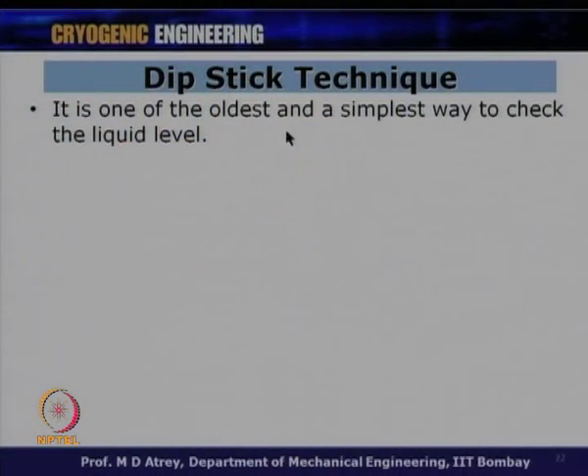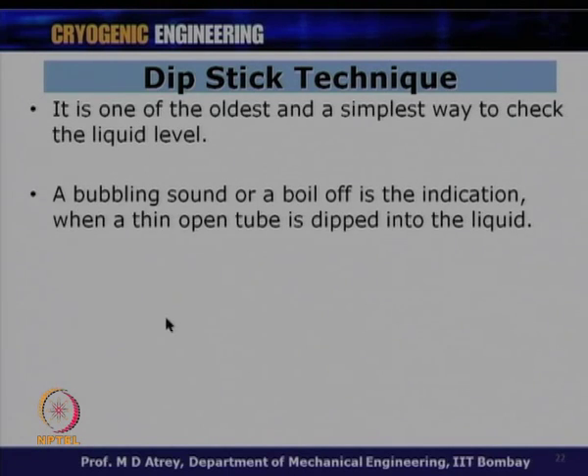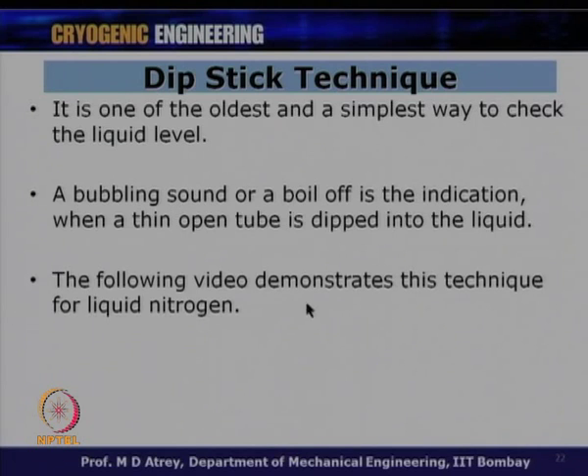Dip stick is one of the oldest and simplest ways to check liquid level — still used for approximate level indication. A hollow tube of stainless steel is inserted into the container. As soon as the open tube touches the liquid, boil-off occurs because the stick is at 300 K; this boil-off comes up through the tube. A bubbling sound is heard at the point the tube reaches the liquid surface, indicating the liquid level.